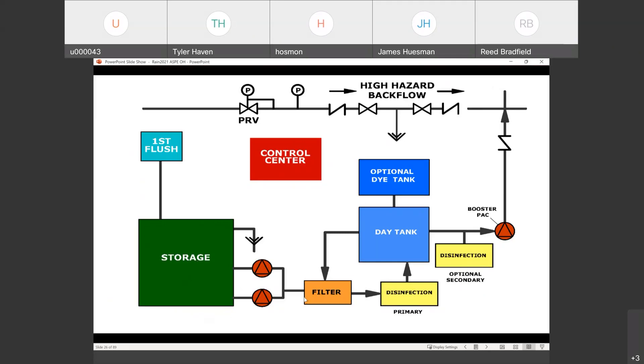When we get above grade, we have the filtration and disinfection — it's designed based on flow. The lower flow from storage through filtration and disinfection keeps it at a manageable size. We could potentially go to a day tank. Some systems pump right through filtration and disinfection directly to the source. Then we have a booster pump to get us through to irrigation, cooling tower makeup water, or whatever we need. There could be optional dye injection in here, and we need makeup water — sometimes you won't have enough storage in the dry season and need some sort of backup water supply for these systems.